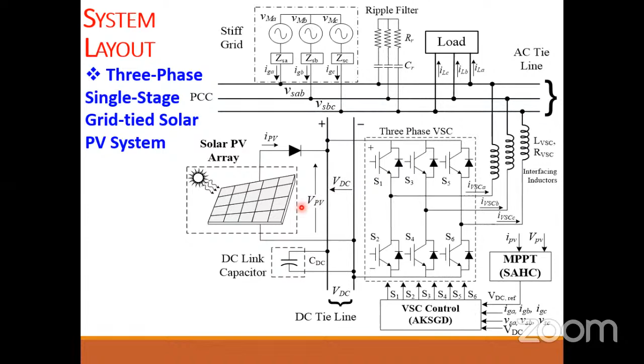In the single stage case, the switch should be selected according to the VOC of this panel, around 850 to 900 volts. But in the two-stage case, the panel is not directly attached to the switch; in between, there is a DC-DC converter. So the switches are selected according to our DC link, plus or minus 5 to 10%, not according to the VOC of the panel. This is another difference between the two-stage and single-stage configurations.